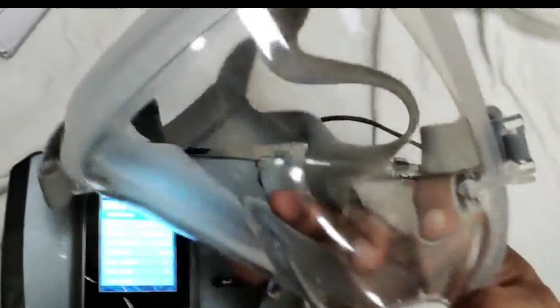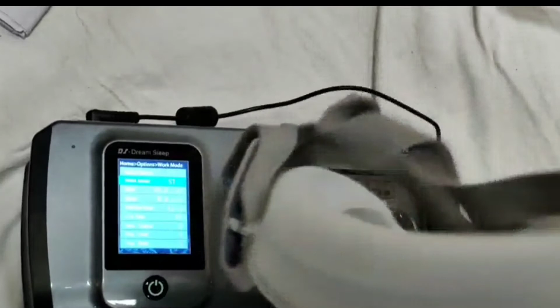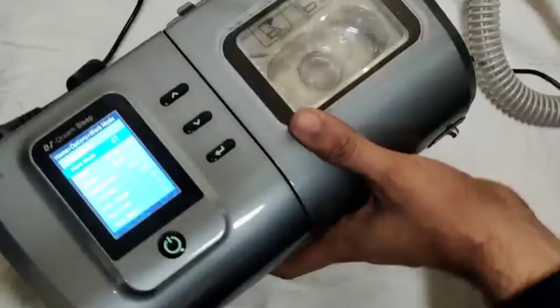So let's come back to the ST mode, the BiPAP mode. So here I have put the IPAP 16 and EPAP 8, and once it's done, I would just press the power button and let's see whether it's working or not. Okay, the other thing is that every BiPAP machine comes with piping. You have to put the piping and the mask. Mask comes in two different types. It's a big mask that covers the whole face. You have to put the tubing correctly and fit the mask correctly.